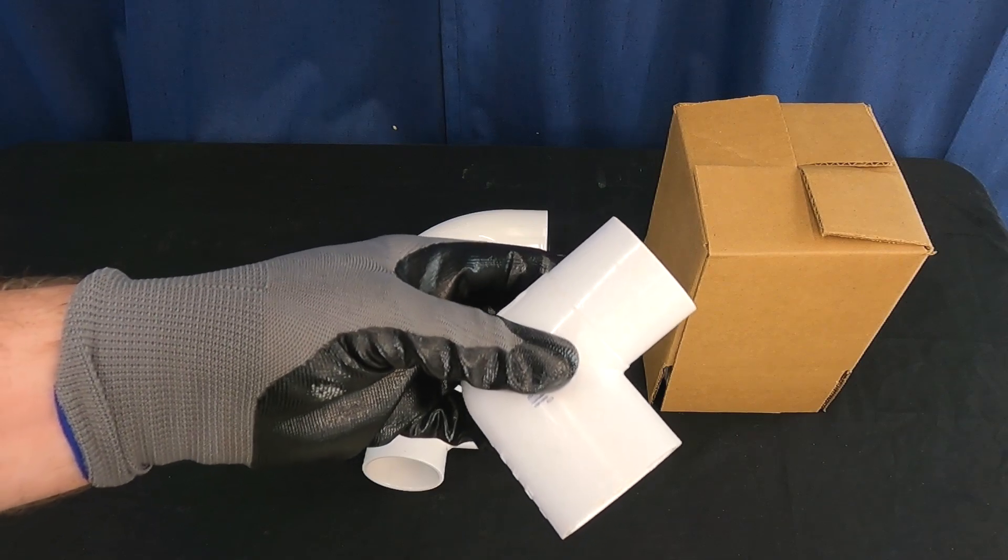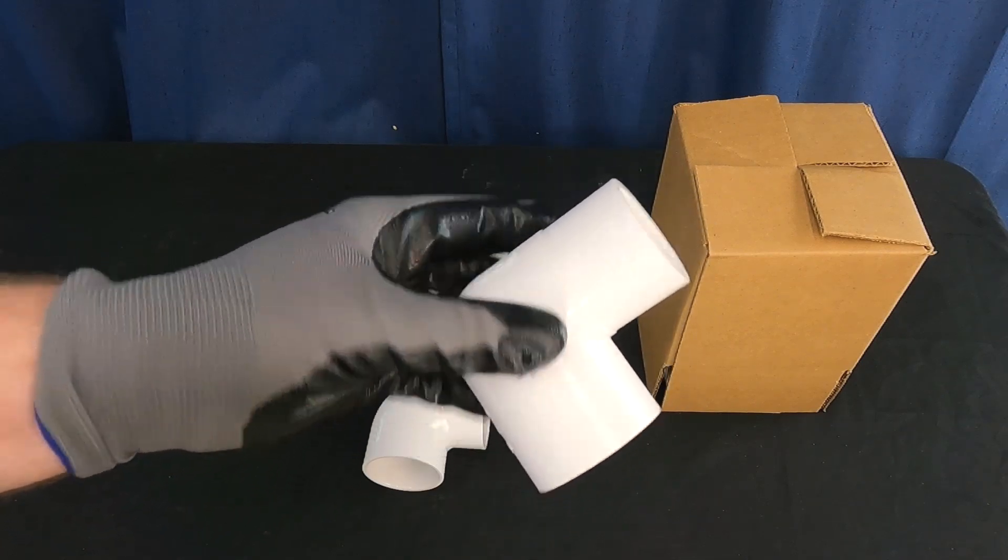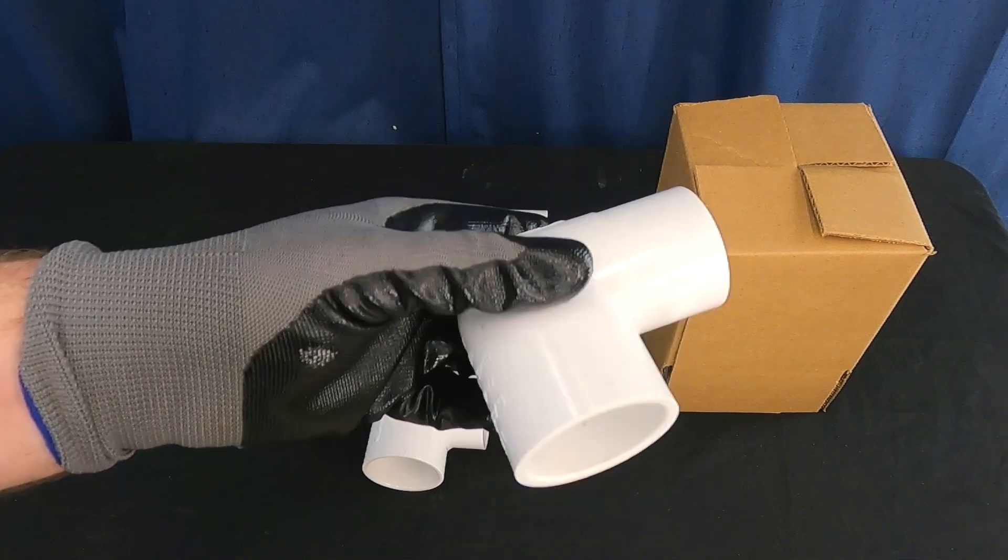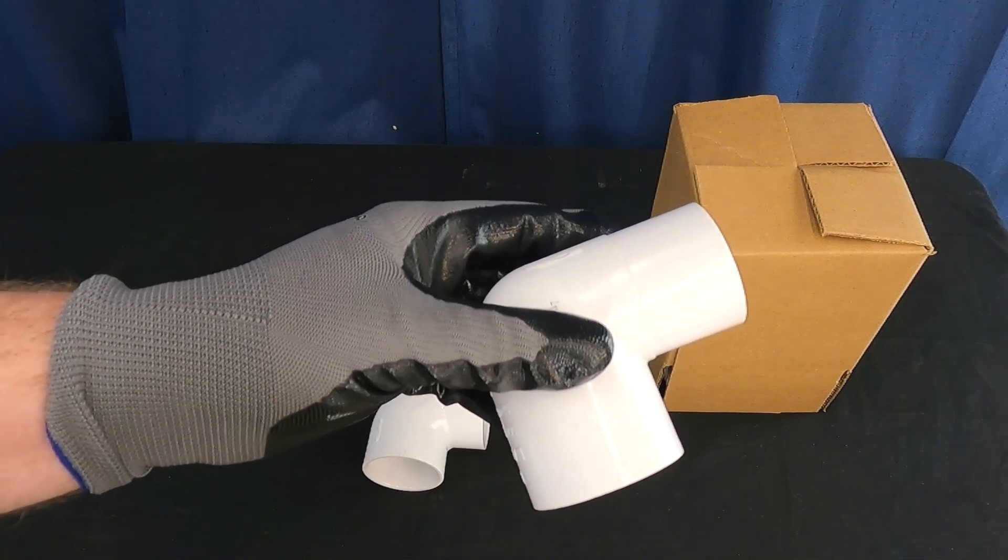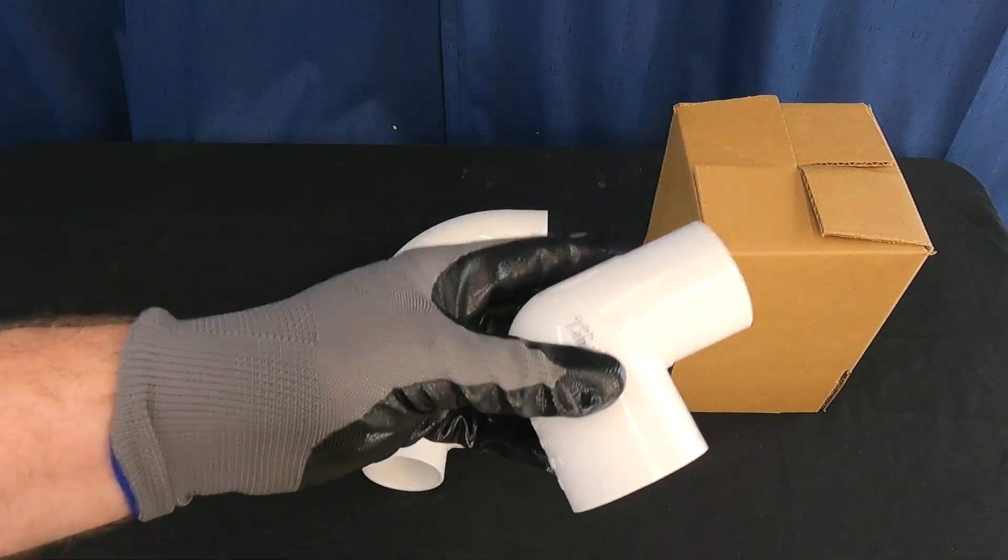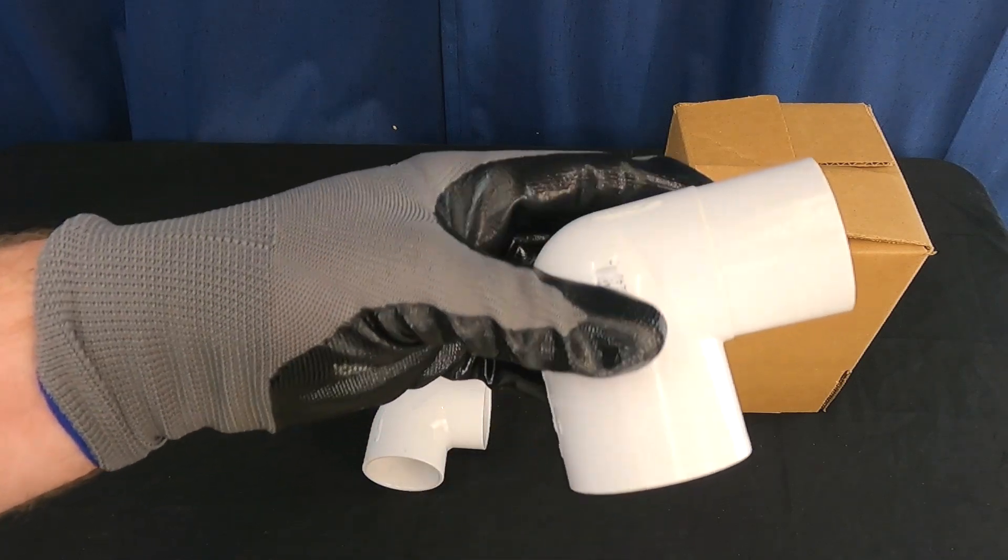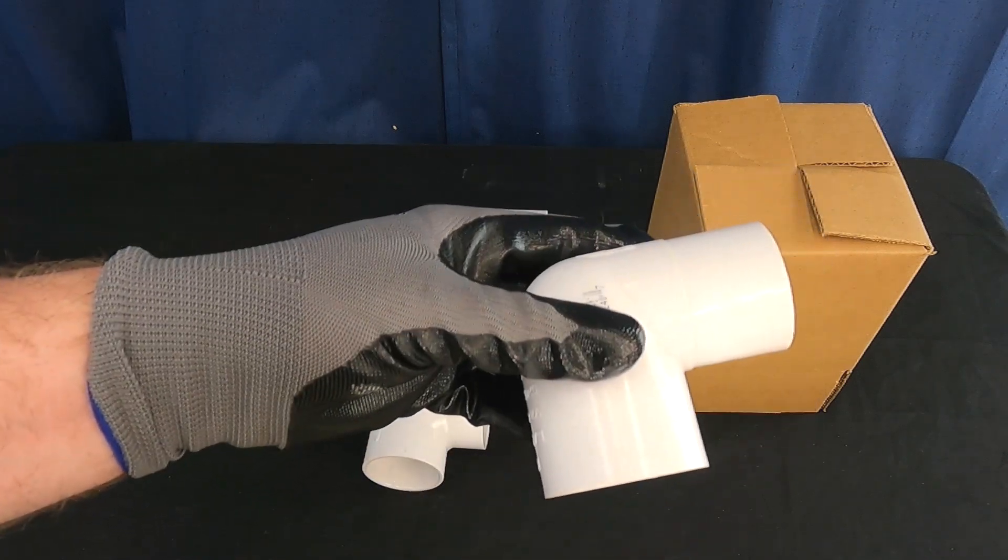So I went on a little bit of a tirade the better part of a decade ago, made a lot of content about these because builders and installers were using these as the only way that they would transition a 90 degree bend. Everything was done with street elbows and it made no sense to me at all. These were more expensive than short radius 90s. They're way worse in terms of the friction loss. They're just a terrible choice all around.